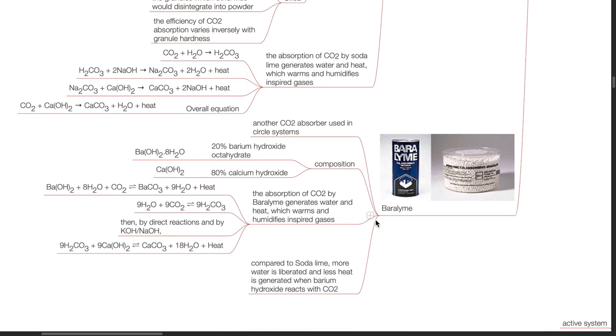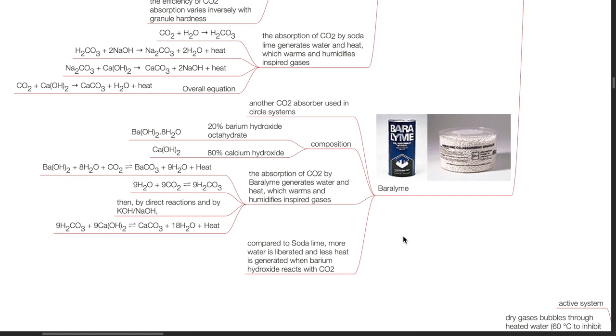Baralyme is another CO2 absorber used in circle systems. Its composition is 20% barium hydroxide octahydrate and 80% calcium hydroxide. The absorption of CO2 by Baralyme generates water and heat, which warms and humidifies gases. The formula: Ba(OH)2·8H2O + CO2 → BaCO3 + 9H2O + heat; 9H2O + 9CO2 → 9H2CO3, then by direct reactions and by KOH or NaOH: 9H2CO3 + 9Ca(OH)2 → CaCO3 + 18H2O + heat. Compared with soda lime, more water is liberated and less heat is generated when barium hydroxide reacts with CO2. For further details, kindly refer to the video on CO2 absorbers.